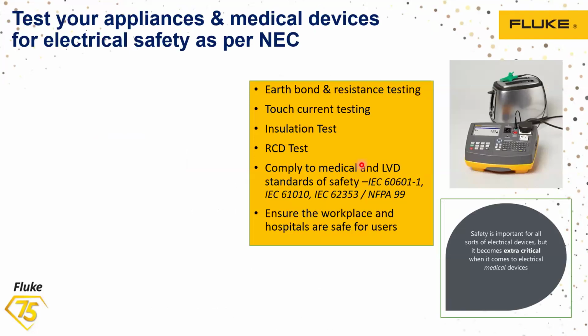The other safety test. Till now we were talking about the electrical installation in your facilities. The other electrical safety test is about checking the appliances, because if you have a facility with your own canteens, you will definitely have class 1 and class 2 appliances, right? Even class 2 appliances need to be tested for safety purposes, because we are talking about earth bond resistance testing: how much bonding is available between the earthing and the body.